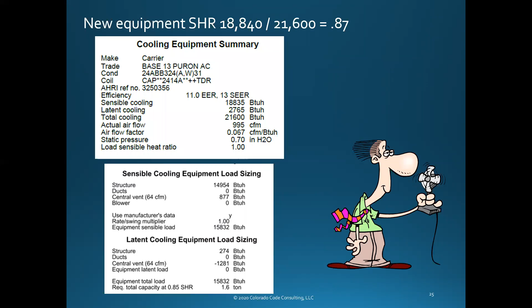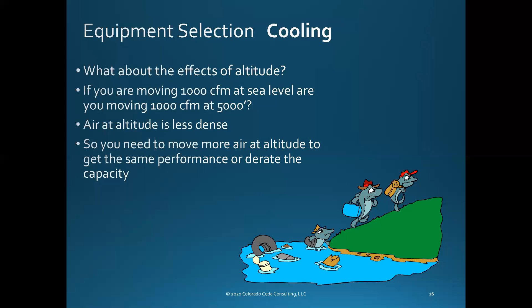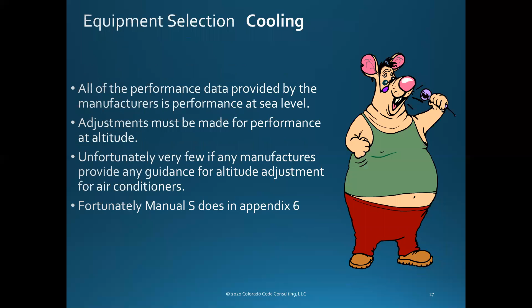So altitude, the whole idea is, are you moving 1,000 CFM at 5,000 feet if you're moving it at sea level? The answer is absolutely you are. It's just that it's the density that counts. So the air doesn't have the same capacity to move heat and cool as it would at sea level. So we've got to adjust, and we won't spend a lot of time on it because you guys are a bunch of lowlanders.